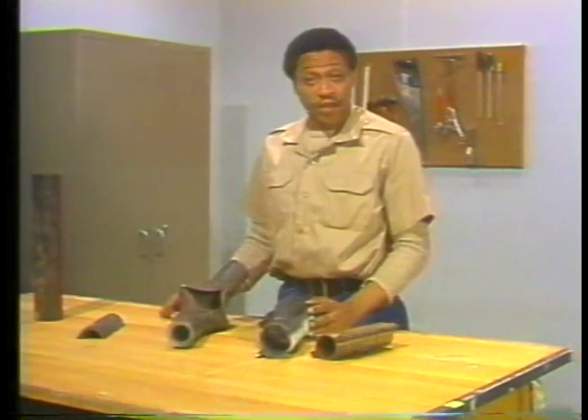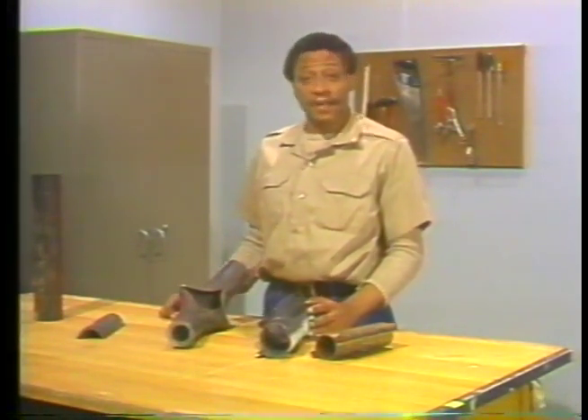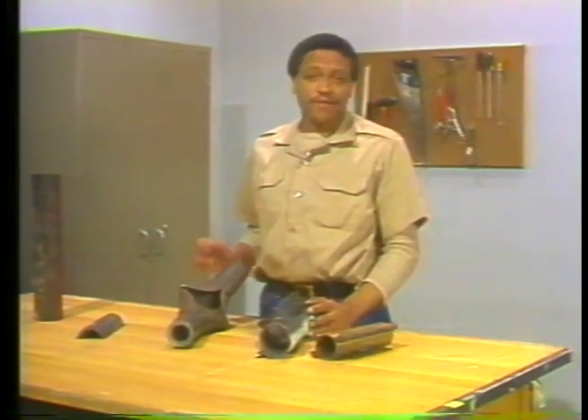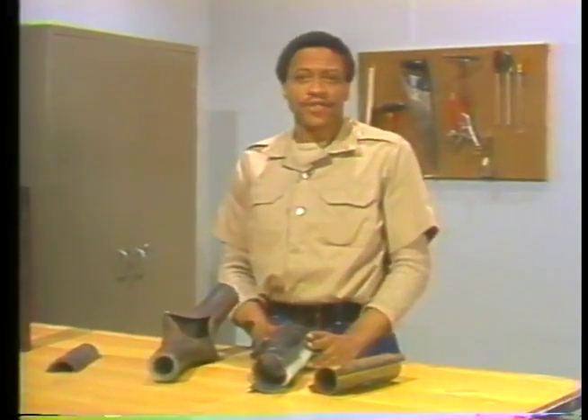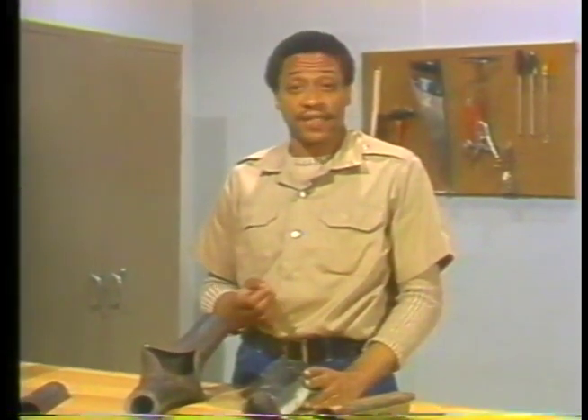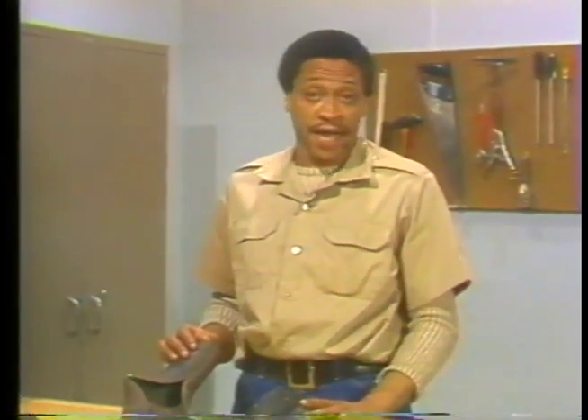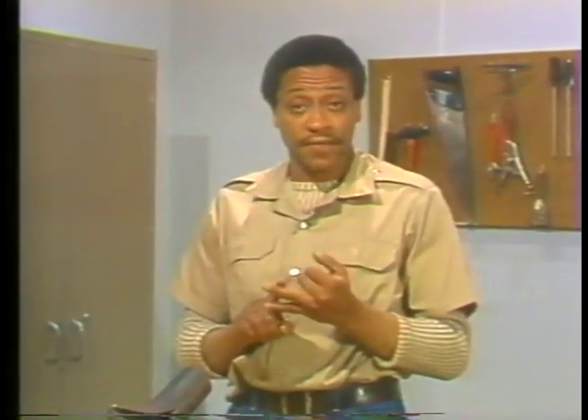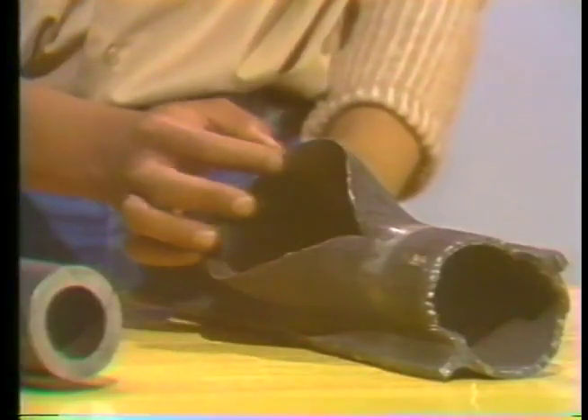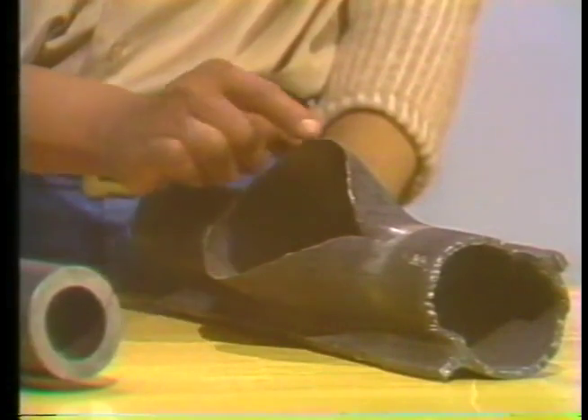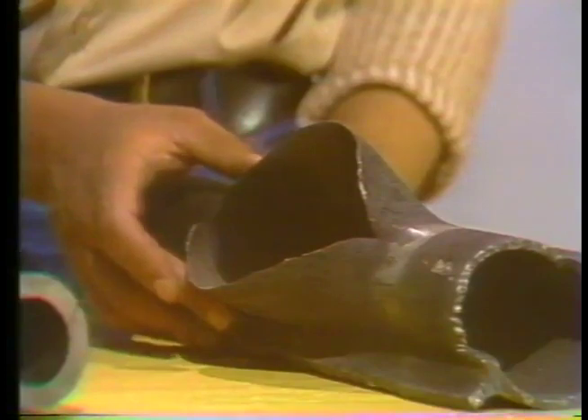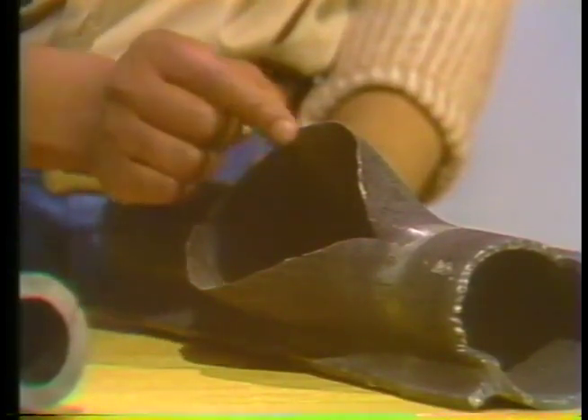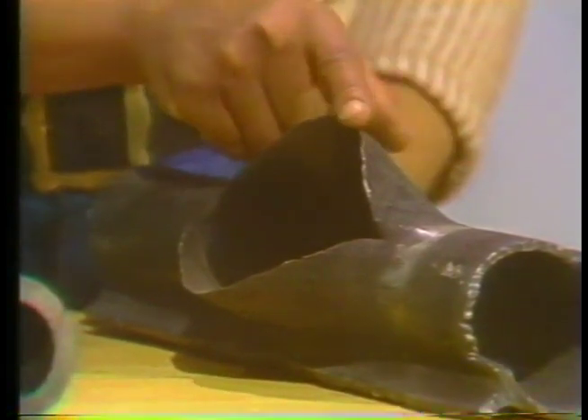Now that we've covered the basic causes of tube failure, let's go over some types of tube failures and deformities. Deformities are irregularities in the tube metal that can lead to tube failure. The first type of failure is a rupture. There are three kinds: thin-lipped, thick-lipped, and double-ended. Thin-lipped ruptures are usually caused by sudden and severe overheating. They look something like a burst bubble, with open lips uniformly tapered to sharp, knife-like edges. There is no evidence of cracking or irregular tearing in a thin-lipped rupture.